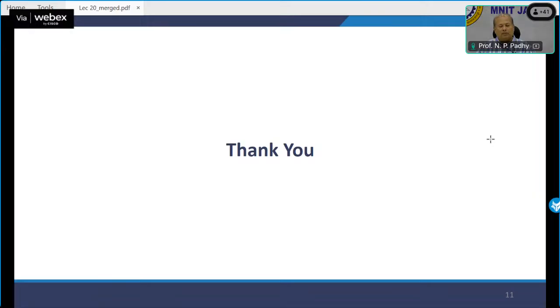I have been told that most of the evening hours, the evening peak, the 200 kilowatt hour is being discharged to the electrical engineering department without consuming energy from the main grid or from the diesel generator. So this microgrid is indirectly not loading the 33 kV substation during peak hours. This is what we would like to highlight out of this activity.